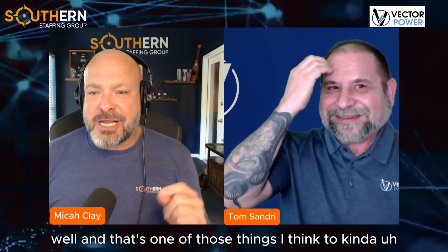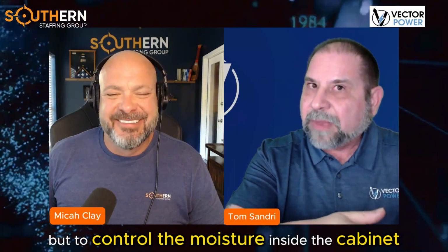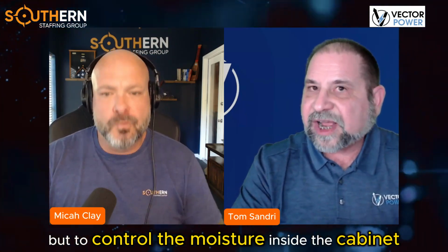Well, and that's one of those things to explain the scope - we're talking microscopic levels in many instances, particles in the air and things like that, would that be correct? Yeah, and again, high humidity, water molecules or moisture on the stress cones - that's why when we talk about metal clad switchgear, the reason we put heaters inside is not to give a comfortable warm environment to the equipment, but to control the moisture inside the cabinet. Because water molecules or moisture accumulating is going to start to form that surface tracking, deteriorating the quality of the surface of the insulator. Instead of having proper clearances, we're providing tracking paths for that current at that point.